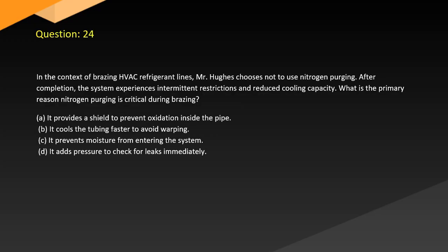Question 24. In the context of brazing HVAC refrigerant lines, Mr. Hughes chooses not to use nitrogen purging. After completion, the system experiences intermittent restrictions and reduced cooling capacity. What is the primary reason nitrogen purging is critical during brazing? A. It provides a shield to prevent oxidation inside the pipe. B. It cools the tubing faster to avoid warping. C. It prevents moisture from entering the system. D. It adds pressure to check for leaks immediately.